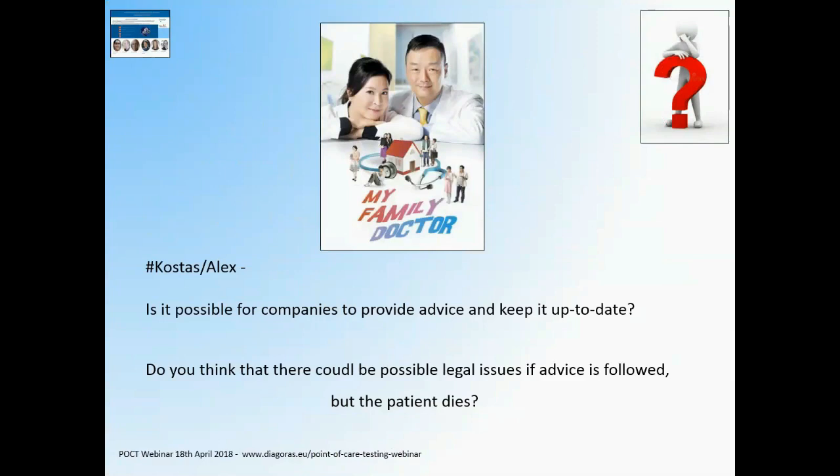Melissa, say something, just from a US perspective. We start getting into these algorithms on how to make decisions and to use the POCT results as advice. In the US, this is no longer a point of care testing device. It cannot be CLIA waived. Really no extra interpretation is required, the way the law states now.